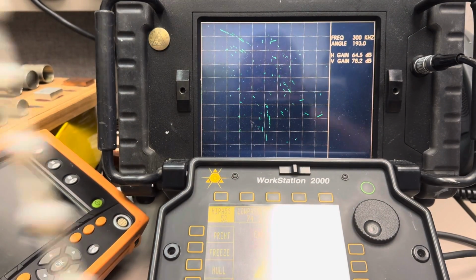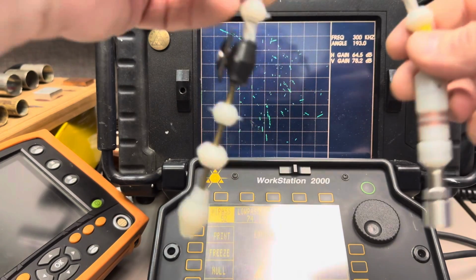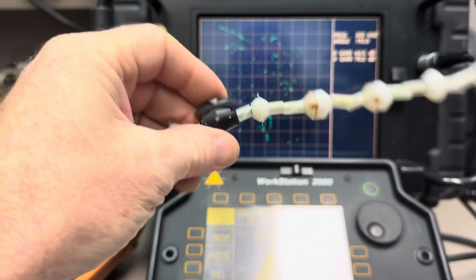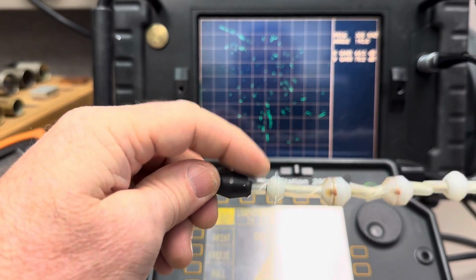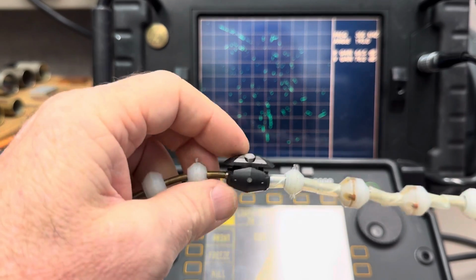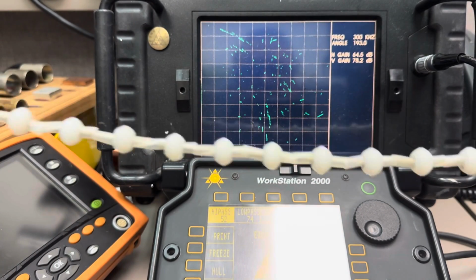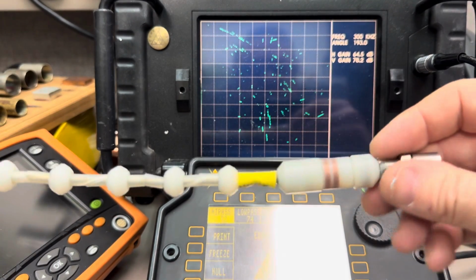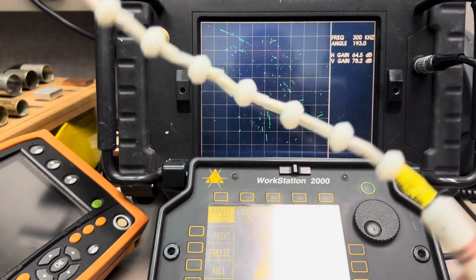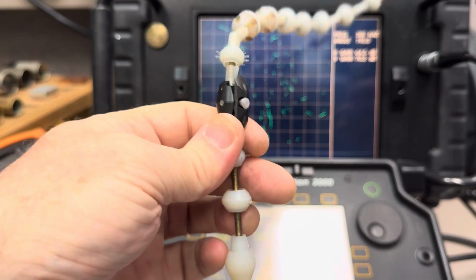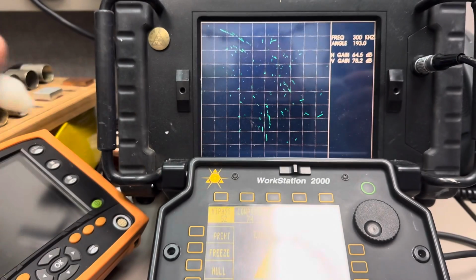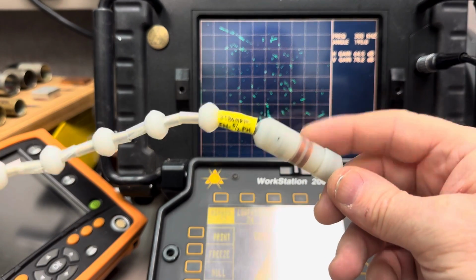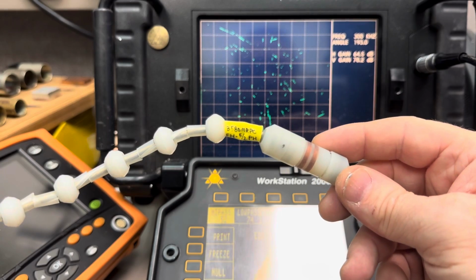And then one last one I've got here. This is actually a combo probe for the U-bends. So it has the single coil. See that little shoe on there? Spring loaded so it can articulate and track over the surface of the ID of the tube. And then down here, about 2 feet away, you've got a set of bobbin coils. So in one pass of the probe, you can get the very precise surface riding pancake or plus point coil, and you can also have the normal bobbin coil data.